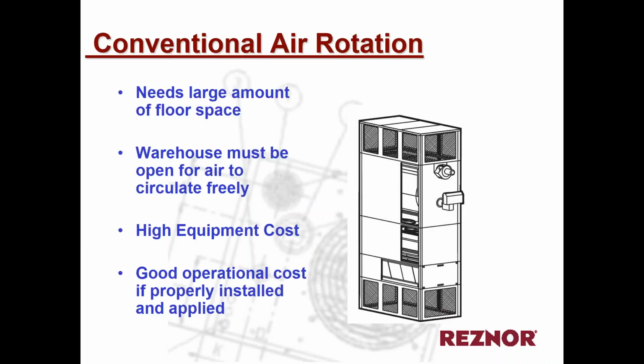This is a view of what an air rotation unit looks like. This picture is hard to scale, but that burner up at the top end is a large industrial burner. These units typically stand about 12 to 15 feet or higher. They're open at the bottom, as you can see, for screened return air back in, and discharge at the top on all 4 sides. Screened allows very open access for that air to be distributed throughout the building. These units also have large propeller fans in them that move that air. Very high amounts of CFM, or large volumes of air, move through these units, and that's how we achieve that air turnover or air rotation.